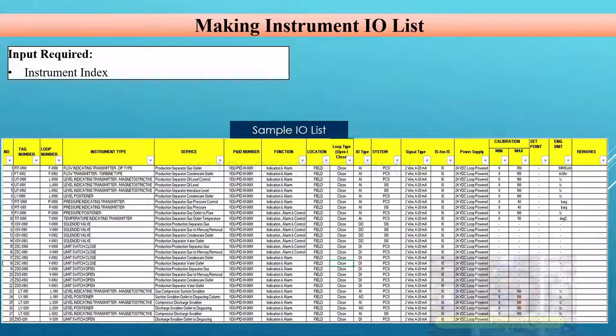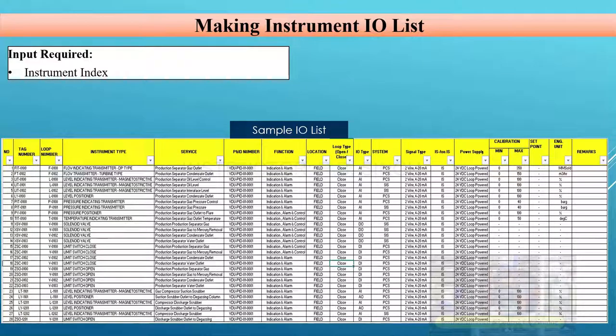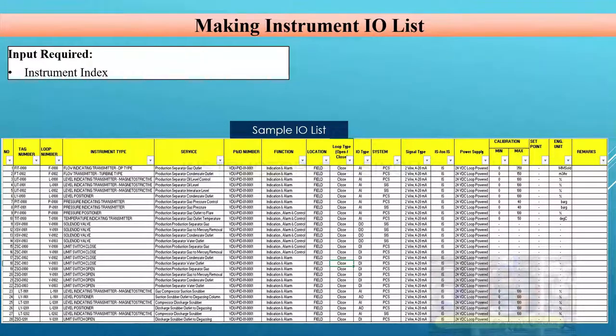Fields already discussed include tag number, loop number, instrument type, service, and P&ID number — all columns from the instrument index. Now, regarding the 'Function' field: whenever you look at any loop, there will be some function — whether the loop is for indication only, for indication and alarm generation, or for indication, alarm, and control (closed loop). For example, a pressure transmitter connected to a control valve forms a closed loop.